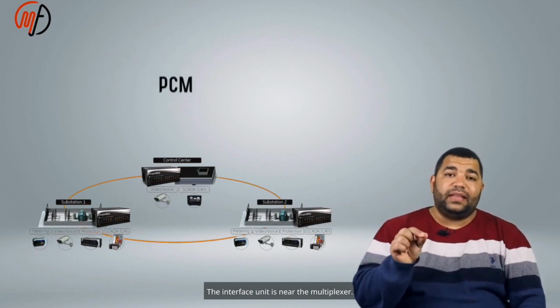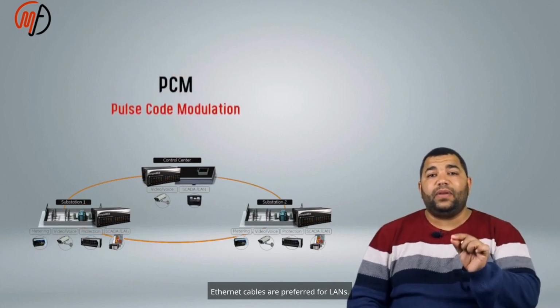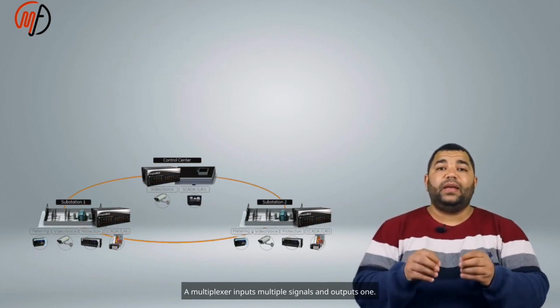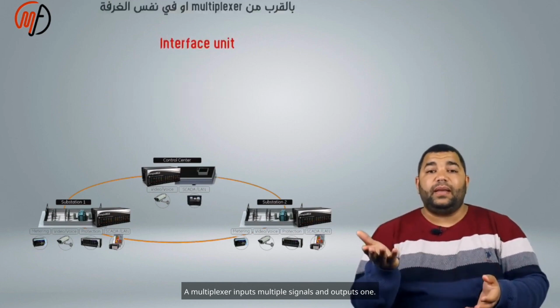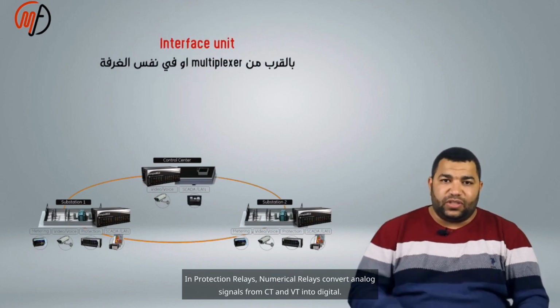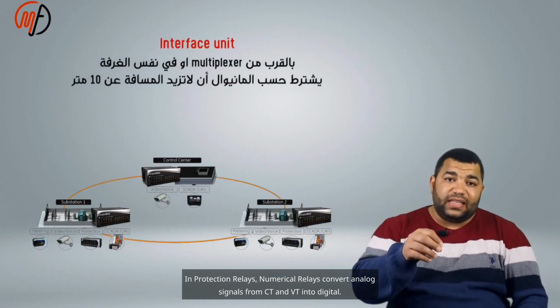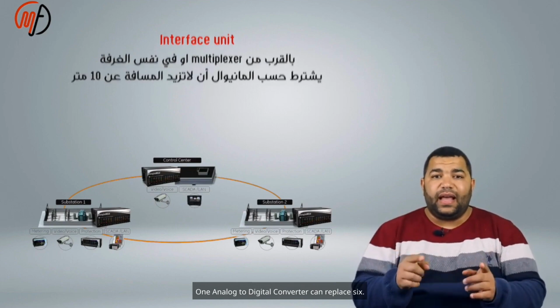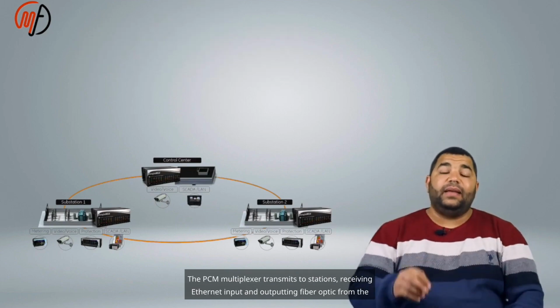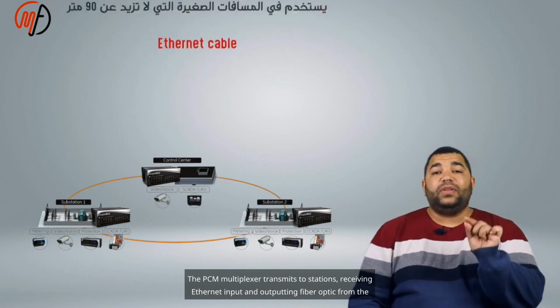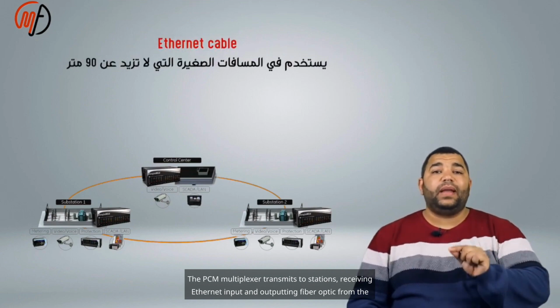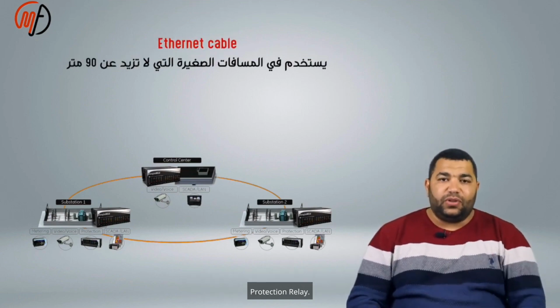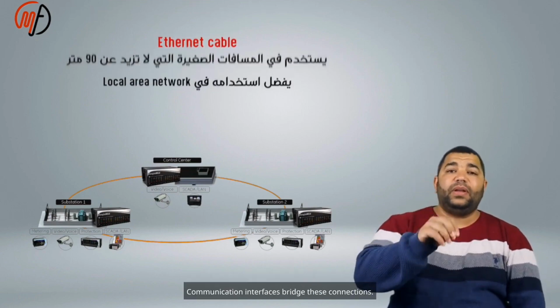The interface unit is near the multiplexer. Ethernet cables are preferred for LANs. A multiplexer inputs multiple signals and outputs one. In protection relays, numerical relays convert analog signals from CT and VT into digital. One analog to digital converter can replace 6. The PCM multiplexer transmits to stations, receiving Ethernet input and outputting fiber optic from the protection relay. Communication interfaces bridge these connections.